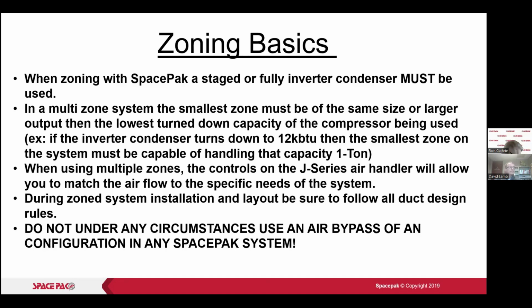do zoning, it's 2 or 3 zones, and we want to make sure that we have an adequate number of outlets for each zone. And there's an equation that we use, and we'll show you that in a second. All right, but we always use a staged, as in 2-stage or fully inverter condenser for zoning. Okay, we don't use a single stage in zoning.